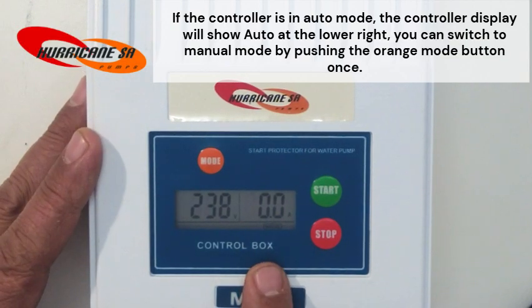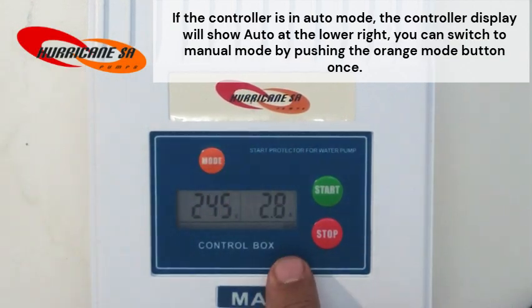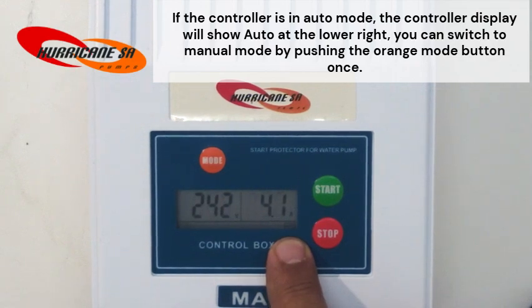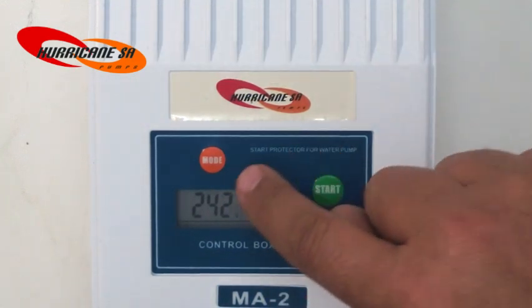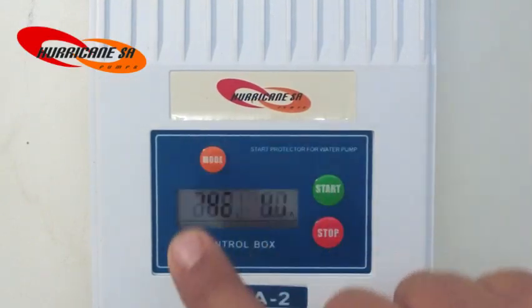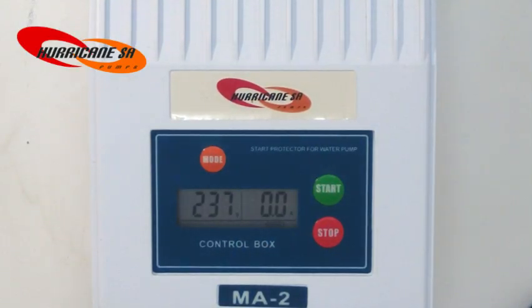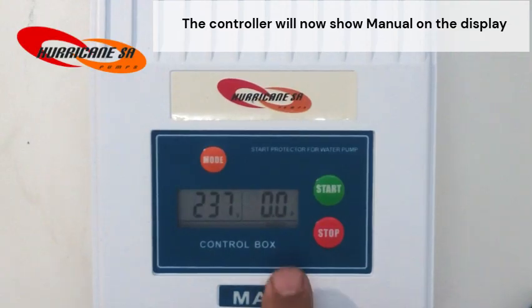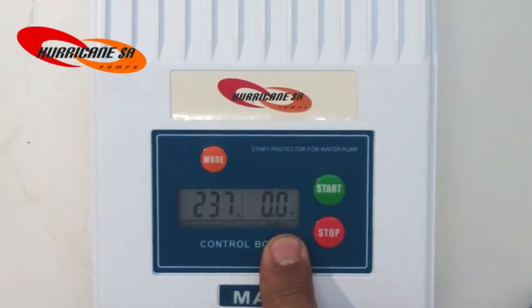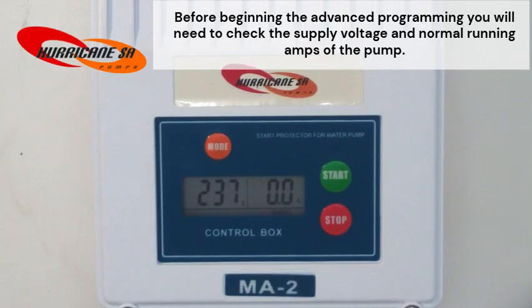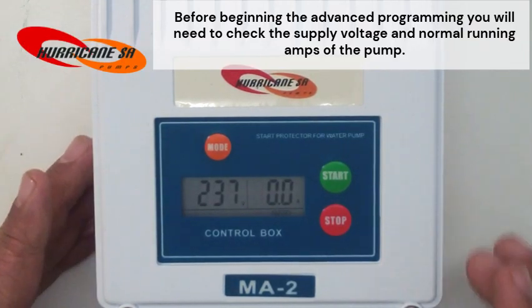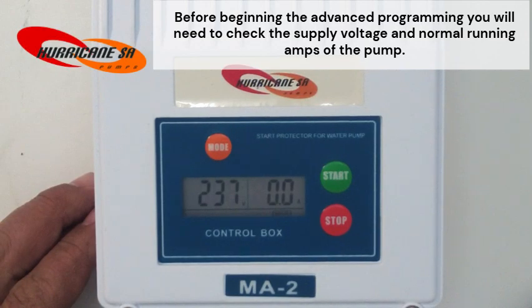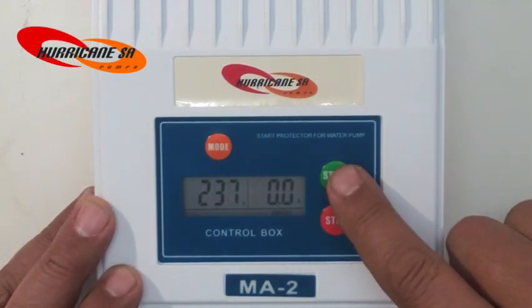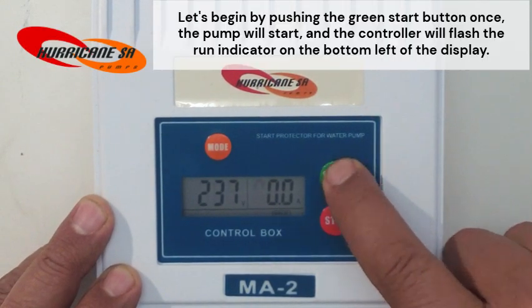If the controller is in auto mode, the controller display will show auto at the lower right. You can switch to manual mode by pushing the orange mode button once. The controller will now show manual on the display. Before beginning the advanced programming, you will need to check the supply voltage and normal running amps of the pump. Let's begin by pushing the green start button once.